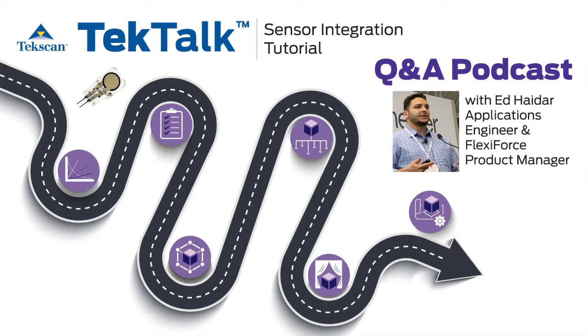Right now, our general recommendation is to aim for a contact pressure of somewhere around 1 psi. Our testing has shown that the repeatability and the characteristics of the sensor are most realized at that minimum contact pressure of 1 psi.